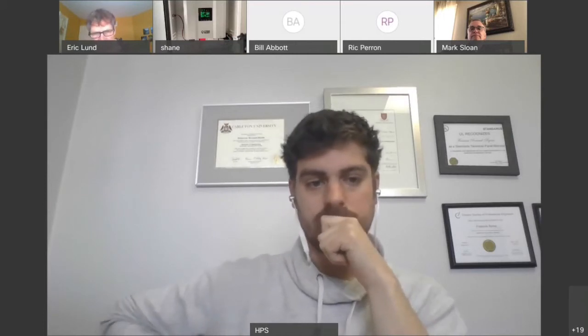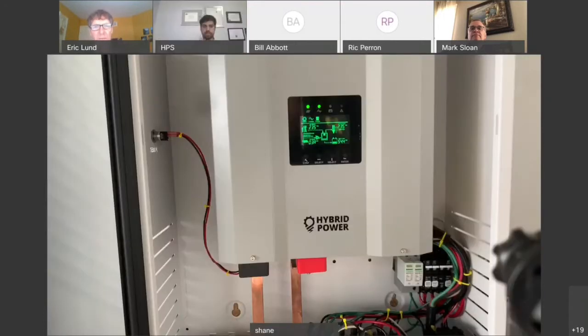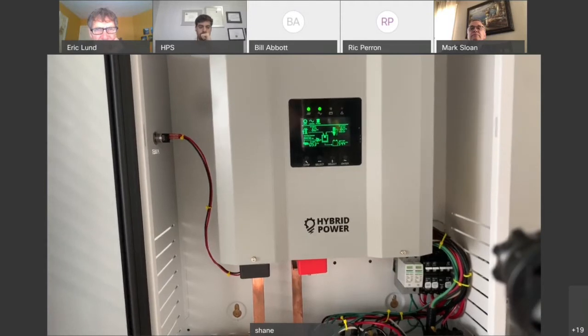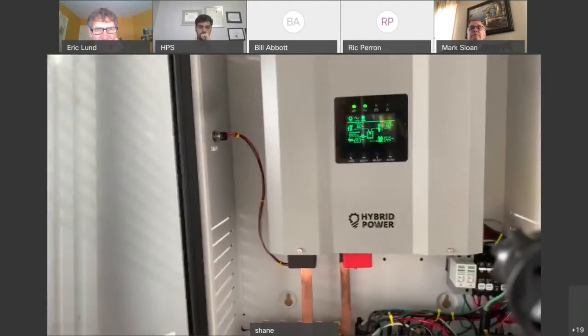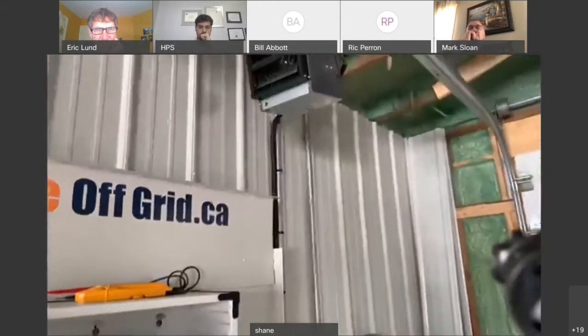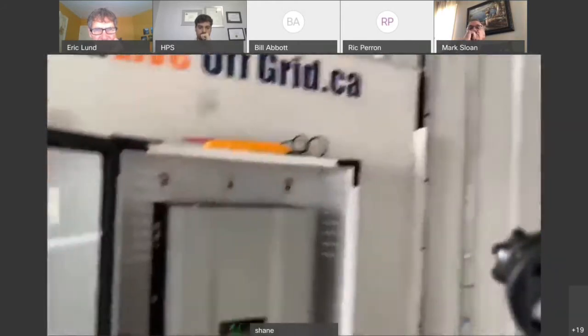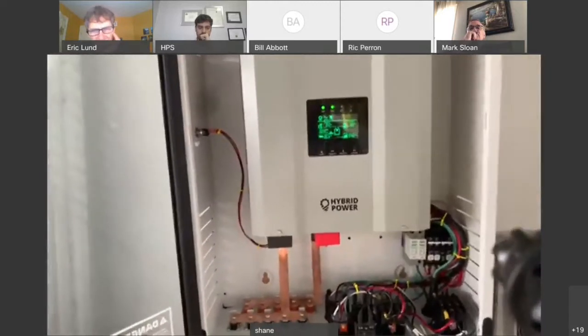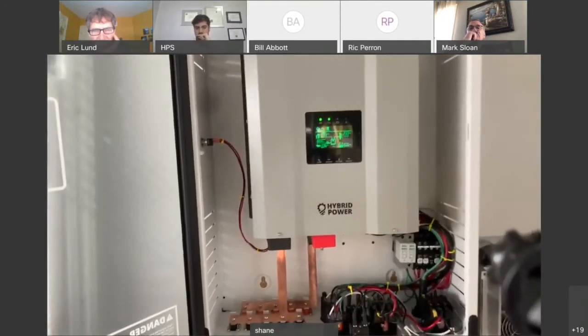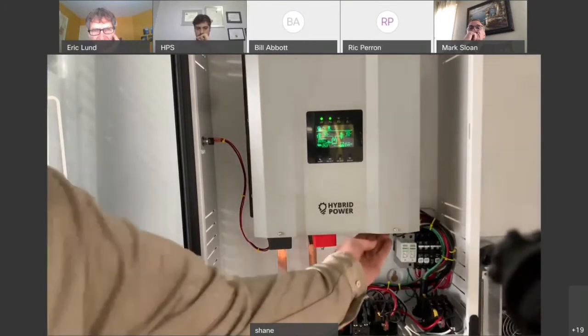So for that setup, you would have a pony panel where you want all your loads to run primarily off solar. You would have to have two different panels, and it's not bi-directional on the AC side. So now that we're charging, you're going to hear the fan come up because it's working. That's fine. The fan's supposed to come on. It's got to cool off the electronics. It's working pretty hard. What I'm going to do now is put a load on with the bypass. I have a 5 kilowatt space heater that's mounted up here, and it's tied into the output of the inverter. That's a pretty large load, so we're going to put it on and see how the inverter reacts.